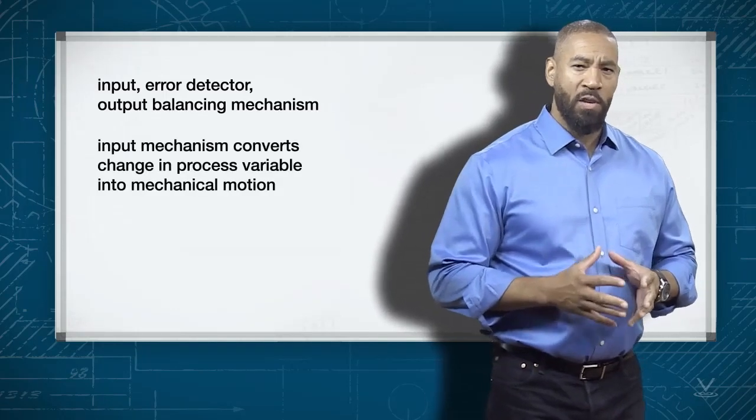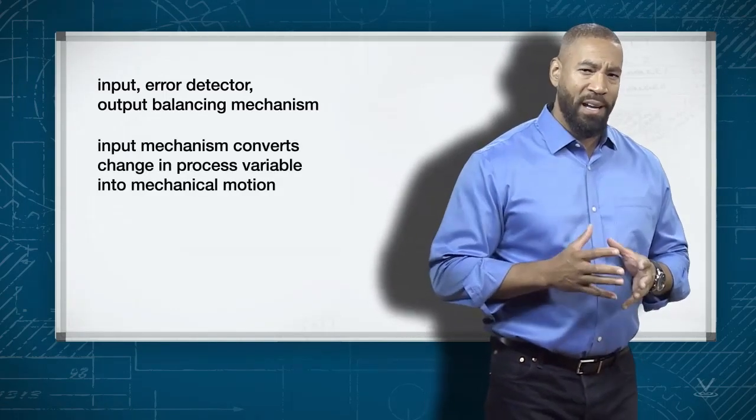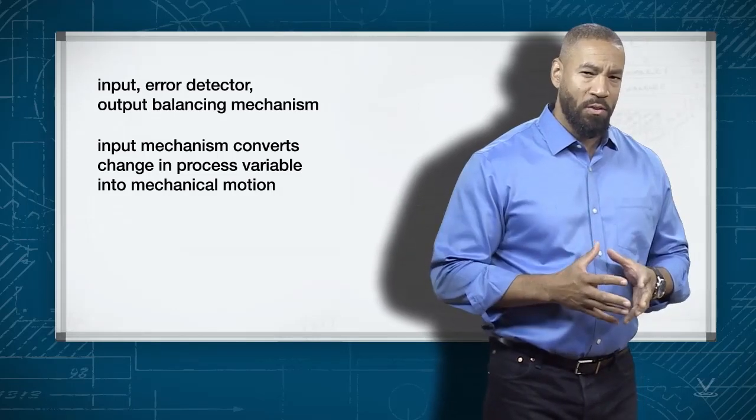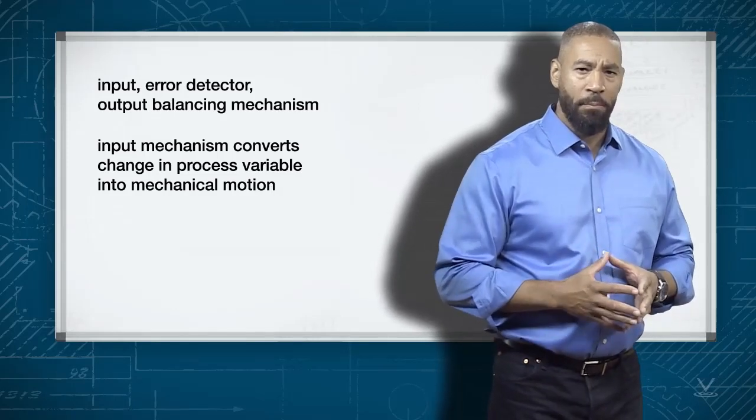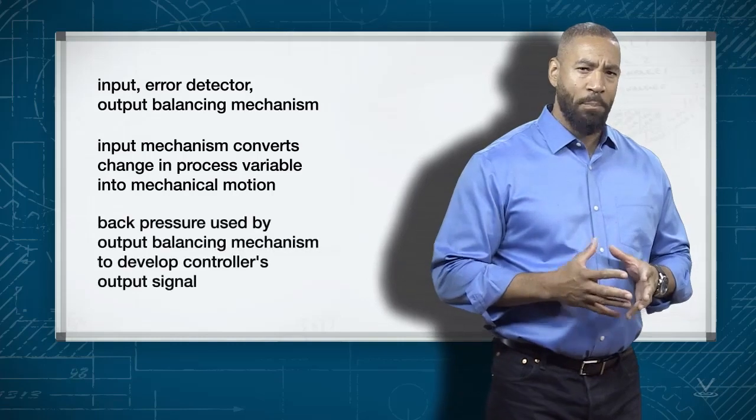An input mechanism converts a change in a process variable into a mechanical motion, which is sensed or detected by the error detector. The output from the error detector, called back pressure, is used by the output balancing mechanism to develop the controller's output signal.